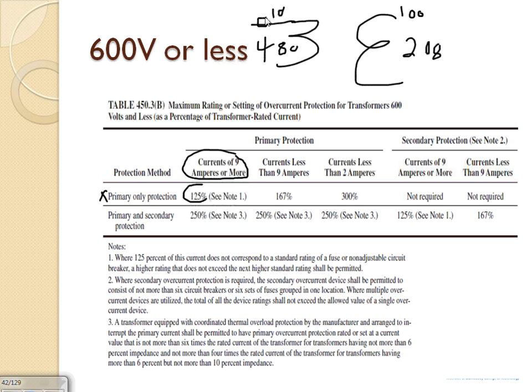What, 12.5, right? It's not a standard, so the next standard is 15 amp. Why do I go up? Because if you guys look at note number 1, it says if it doesn't correspond to a standard... So could you please not go to the bar and start drinking and be mad because they don't make a 12.5 amp fuse for you. Don't go spend an arm and a leg for Bussmann so they can make you a special 12.5 fuse. Go up already. Right? So that's the primary.